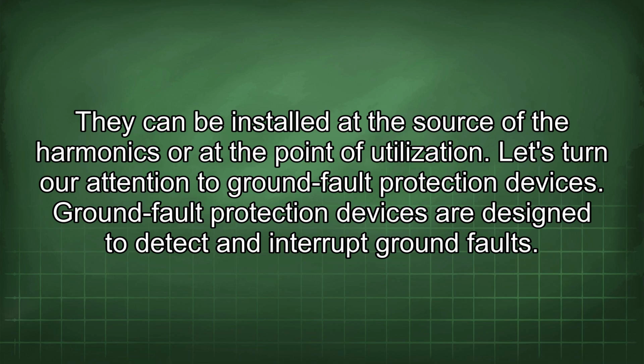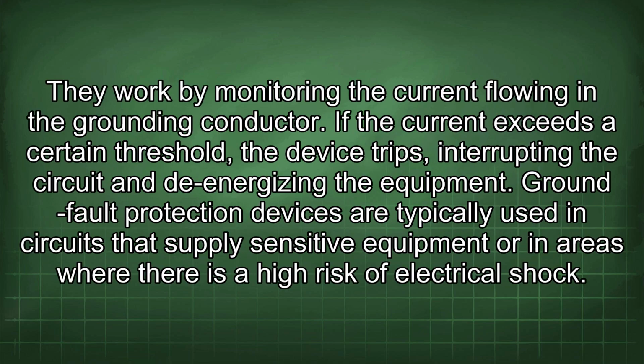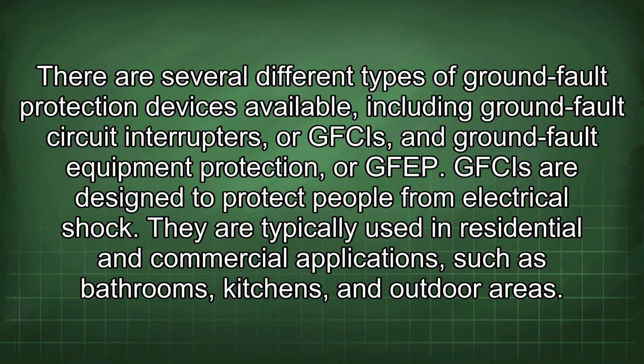Let's turn our attention to ground fault protection devices. Ground fault protection devices are designed to detect and interrupt ground faults. They work by monitoring the current flowing in the grounding conductor. If the current exceeds a certain threshold, the device trips, interrupting the circuit and de-energizing the equipment. Ground fault protection devices are typically used in circuits that supply sensitive equipment or in areas where there is a high risk of electrical shock. There are several different types of ground fault protection devices available, including ground fault circuit interrupters, or GFCIs, and ground fault equipment protection, or GFEP.